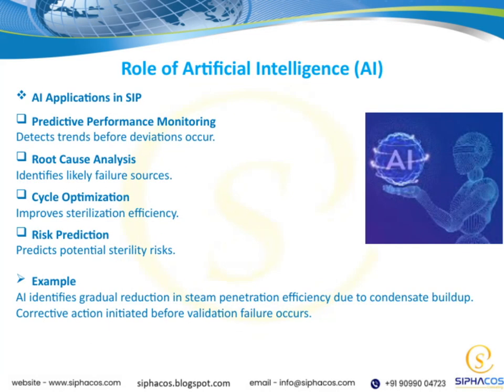Let's talk about how artificial intelligence plays a role in the sterilization improvement process. AI helps us stay ahead by spotting trends before anything goes wrong — that's predictive performance monitoring. It also digs deep to find the root causes of issues, so we're not just treating symptoms. Then, AI optimizes the entire cycle, making sterilization more efficient. It even predicts risks to sterility before they become problems. For example, AI can detect a slow drop in steam penetration caused by condensate buildup, prompting corrective action before a validation failure happens.